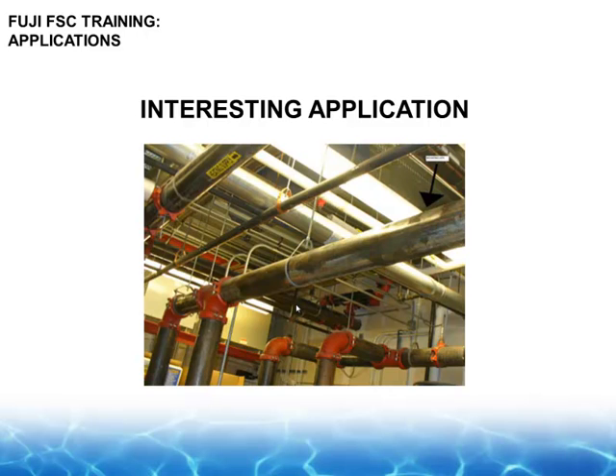And then there are the trick applications. Go to a big box store and look up and you would just see gorgeous plumbing across the ceiling there, just perfectly laid out, picture perfect, and they'll have some of these bright colored connectors on them, and the connectors work absolutely fabulous, but they do have a surprise. The way that they're attached to these thin wall carbon steel pipes here is they tend to ferrule the ends of the pipe.